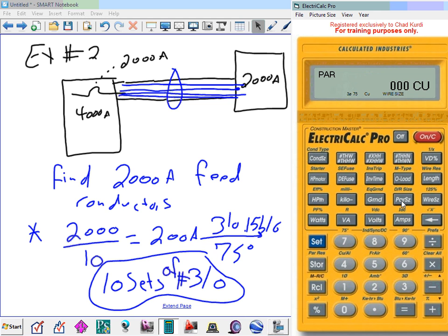Did you guys hear me? I decided to put all these 10 circuits in one conduit. Cool? Everybody's okay with that? Normally you would never do that. You put one circuit, three phase and neutral, in one conduit. 10 conduits, 10 circuits, 4 conductors in each circuit, 3/0 each. Done. Okay, so that's what we normally would do.